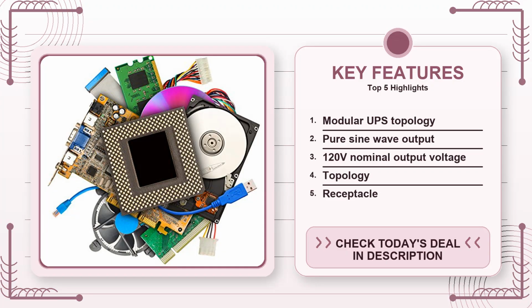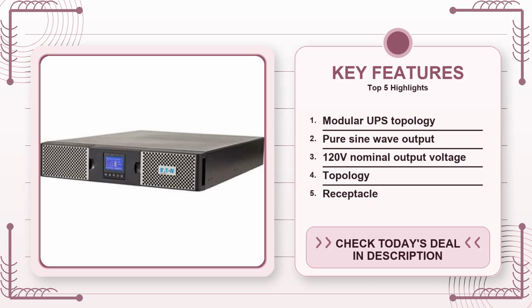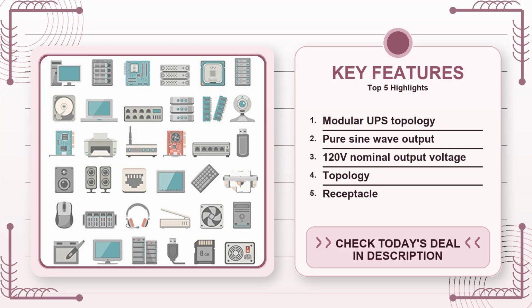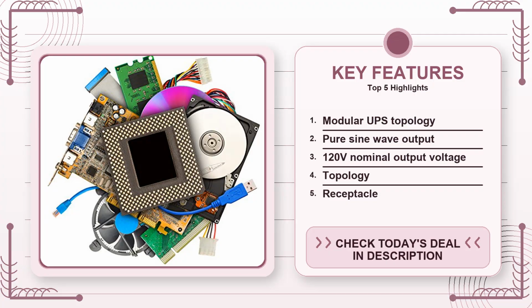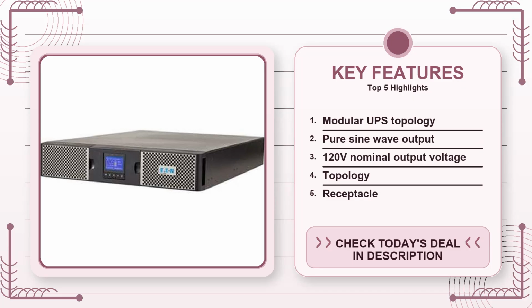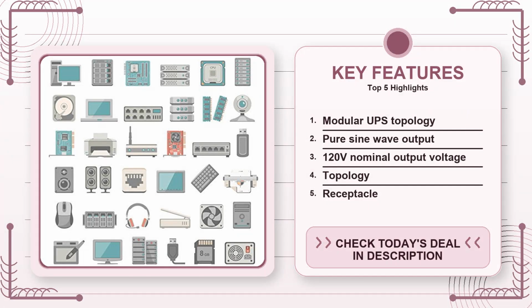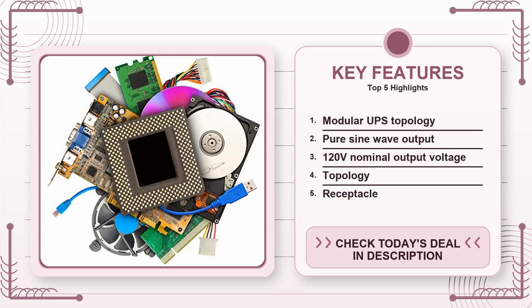Speaking of remote management, the 9PX includes a network card slot. You can add an Ethernet interface and integrate it with EATON's Intelligent Power Manager (IPM) software, or with third-party SNMP tools. In real-world deployments, that means you can have the UPS send an email when battery capacity falls below 20%, or you can script a graceful shutdown across multiple servers. The trade-off is that you have to purchase the network card separately if you want that functionality, adding a modest extra cost. If you're fine with the basic USB connection to a single server, you'll miss out on the broader monitoring capabilities that larger IT shops typically rely on.